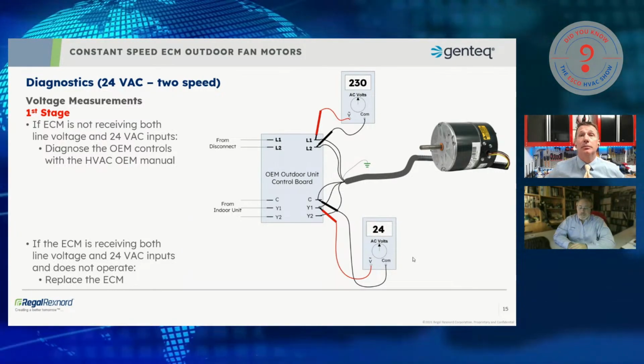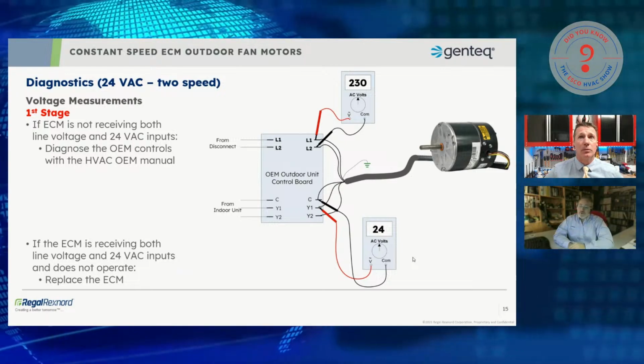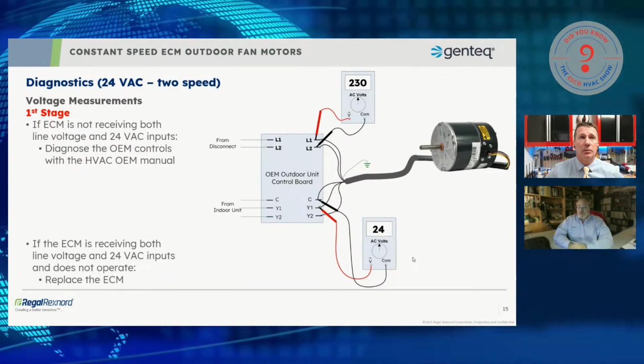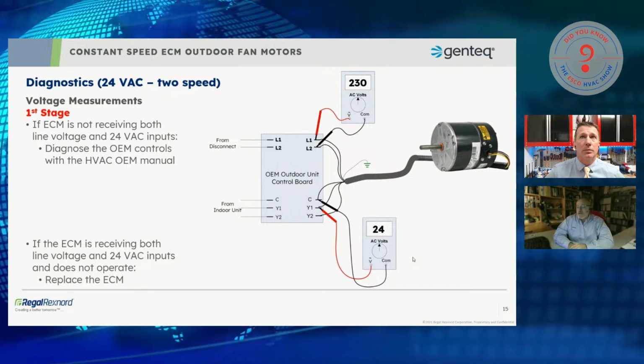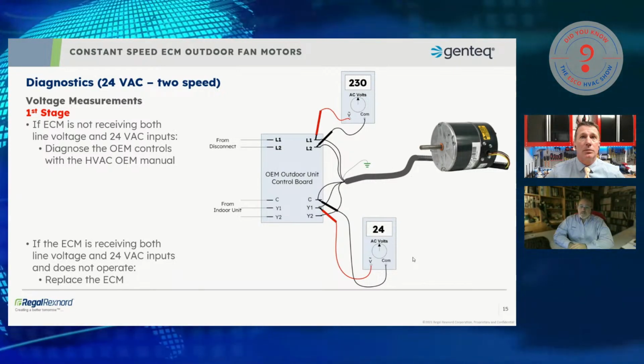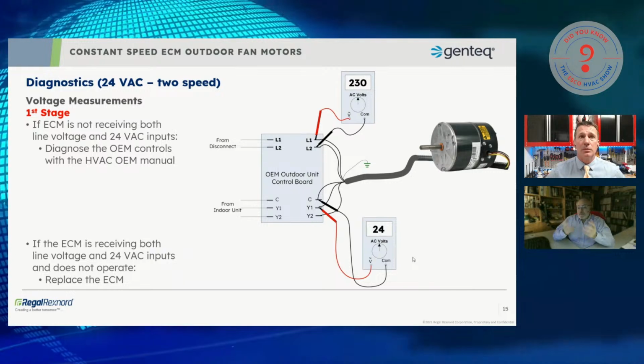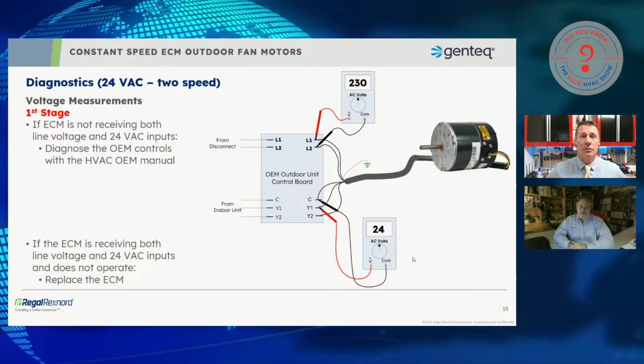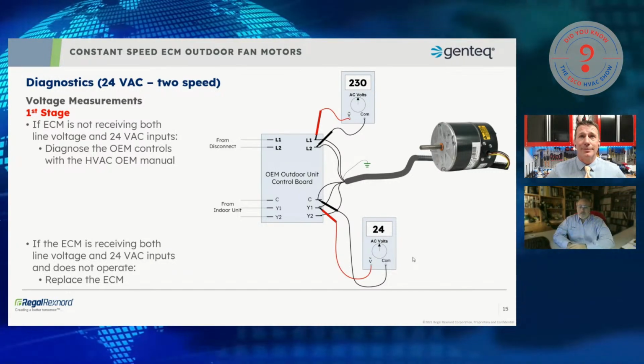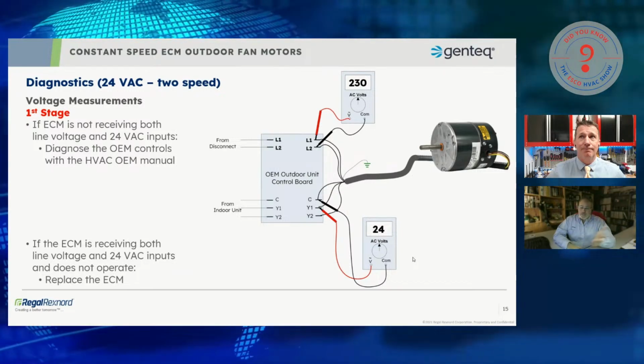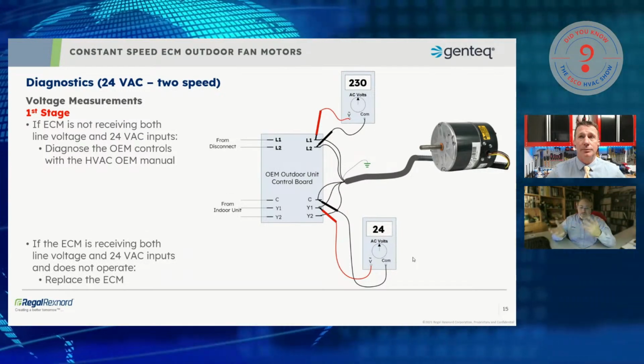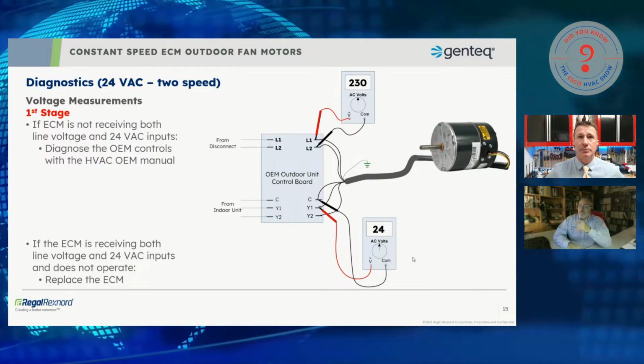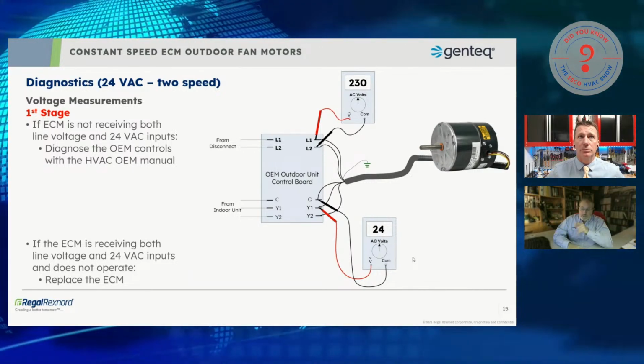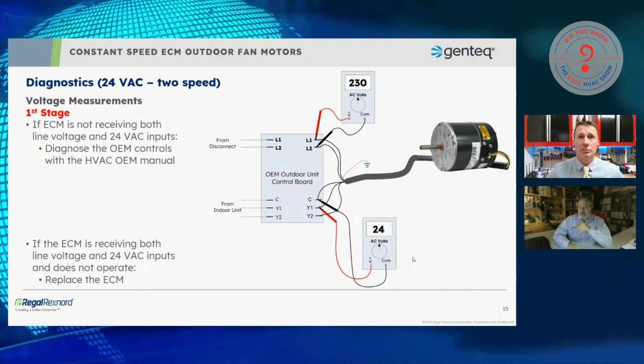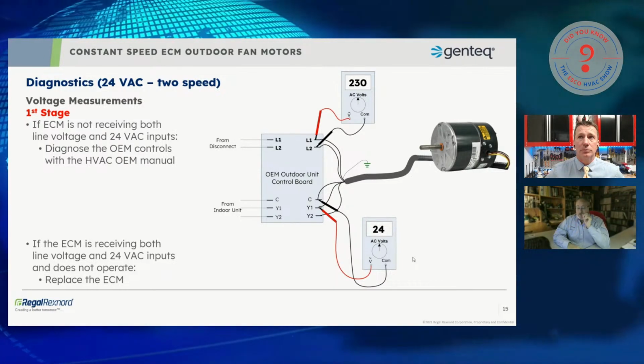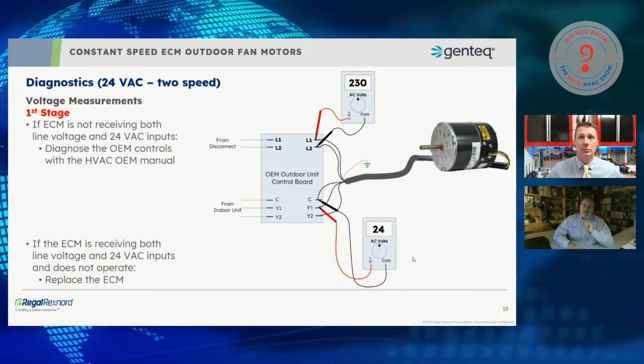Yeah, absolutely. So now that we're on the 2-speed motor, and this bit of conversation will apply to the PWM motor as well, if I do have a system that seems to be underperforming, this is where we're going to maybe talk a little bit about the refrigeration side of the system. So let's say my superheat and my subcool aren't aligning. My head pressure switch is tripping. Maybe I'm just throwing out some refrigeration side what ifs. That's where it might be valuable to know that this is a 2-speed motor, and you may be in second stage operation.